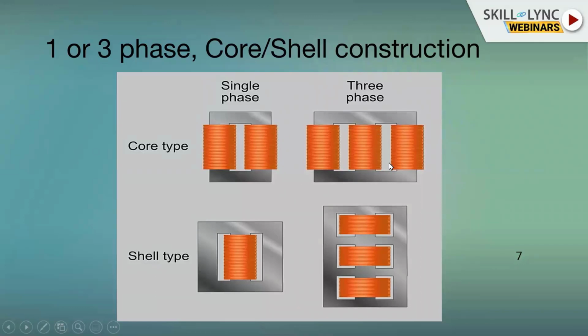And you can see here, one simple thing: in a three-phase transformer, where you have R-Y-B limbs, there is no return magnetic core. Why? Because typically the three phases' current or voltage or flux add up to zero under normal operating conditions. So there's no need for a return limb here for the magnetic flux to go through. At any one point, the flux produced by one particular phase gets returned in the other two phases.